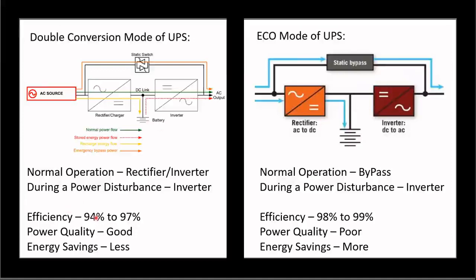Now, also the efficiency. As power is going through these converters, this is an inverter, and getting a pure sinusoidal wave from an inverter is not easy. So efficiency here is 94% to 97%, while here the efficiency is 98% to 99%, because power is not coming through here. Mostly power is coming through the static bypass.